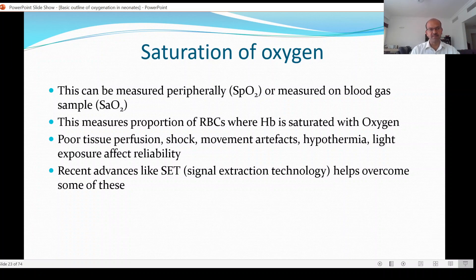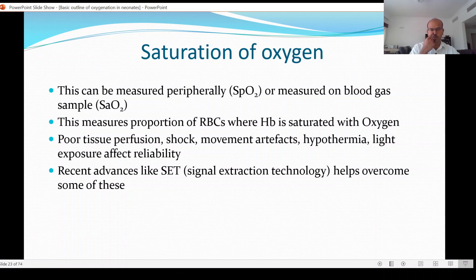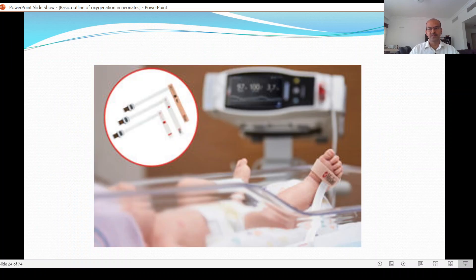Because pulse oximetry depends on pulsatile flow, any situation affecting tissue perfusion — such as shock, movement artifacts, hypothermia — may affect reliability. Light exposure may also affect accuracy. There are recent advances such as signal extraction technology in the Masimo monitor, which helps overcome some of these issues: quicker averaging time without affecting accuracy and reduced movement artifacts.